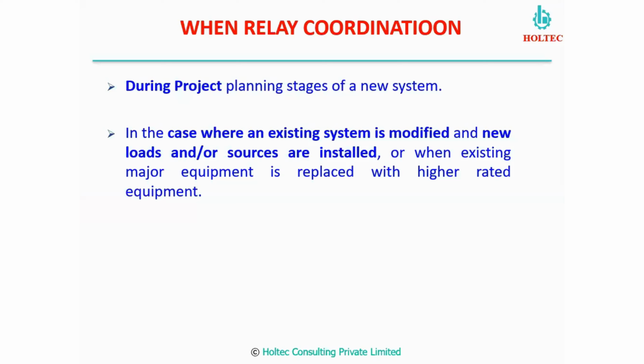Third, there is one more condition where you can redo the relay coordination: if you are facing abnormal trippings, which means tripping of the incomer without identifying a fault in the bus. The fault is actually happening in one of the motors connected to the bus and my incomer is tripping, or any motor circuit breaker relay is operating and we are not able to find any fault, or the protection is not operating as per our desired protection philosophy. Then it is time to check the relay coordination again.